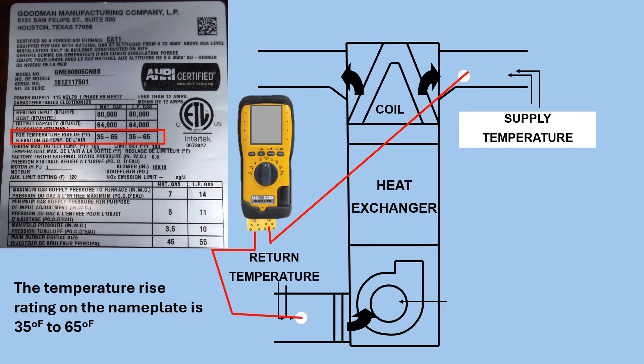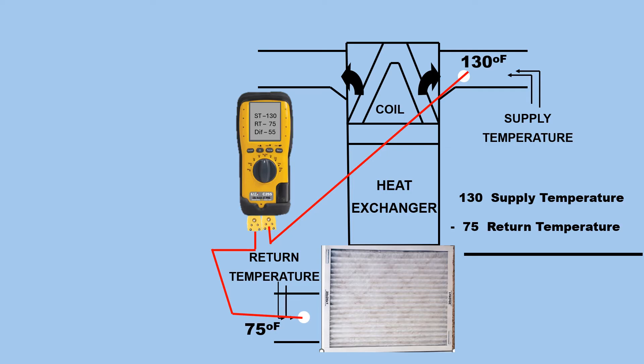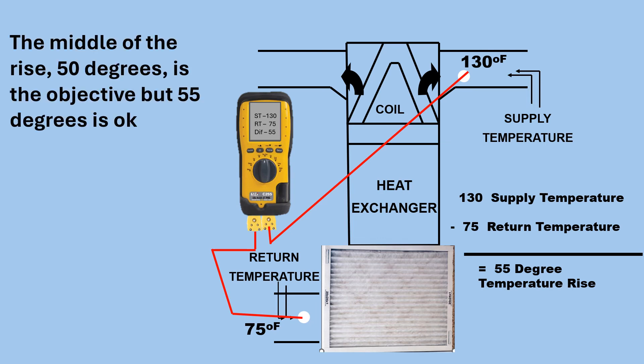So this is where we're going to take our temperature rise. You can see we have our two holes cut and out of the way of the radiant heat. The temperature rise rating on the nameplate is 35 to 65 degrees, as we see in the highlighted space there. So if we have a supply temperature of 130 and a return temperature of 75, that gives us a 55-degree temperature rise. The middle of the range — 50 degrees — is the objective, but 55 degrees is okay.